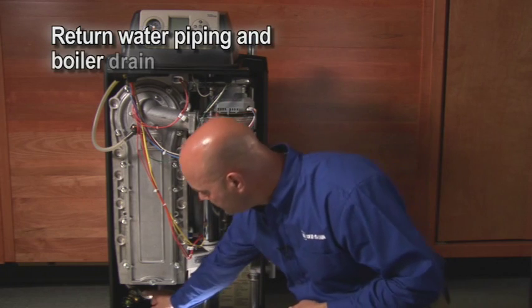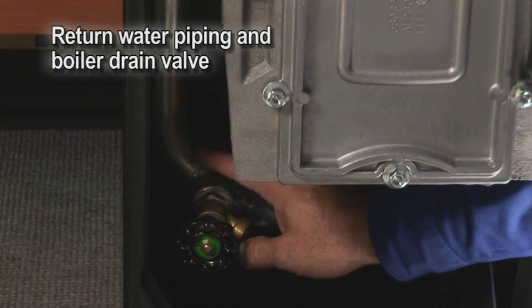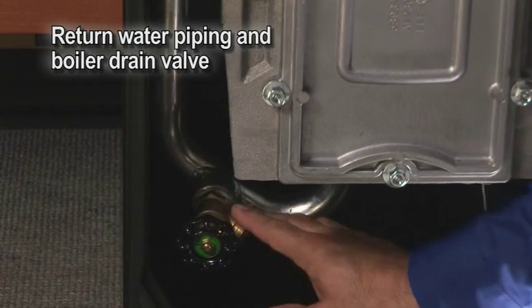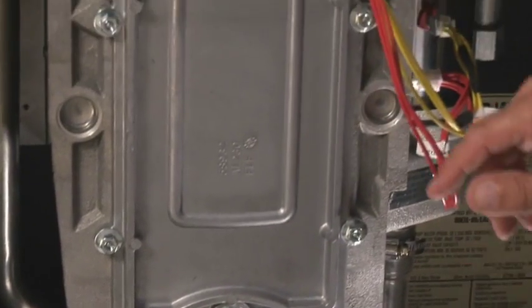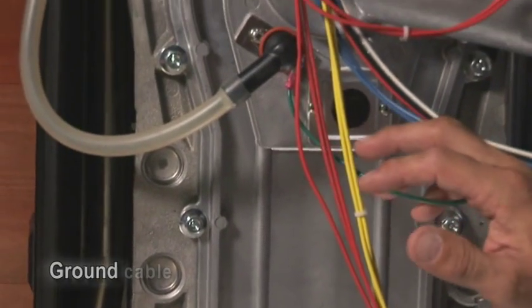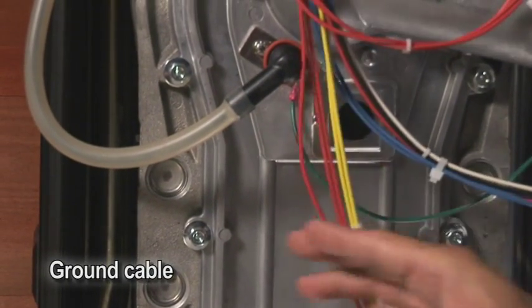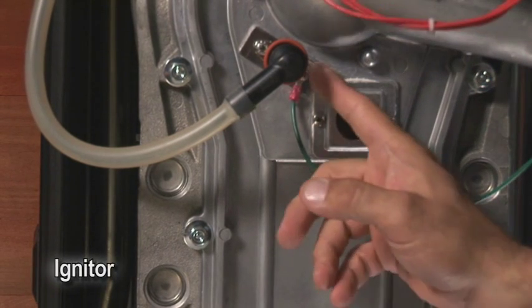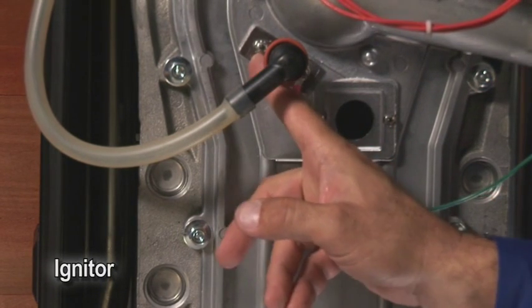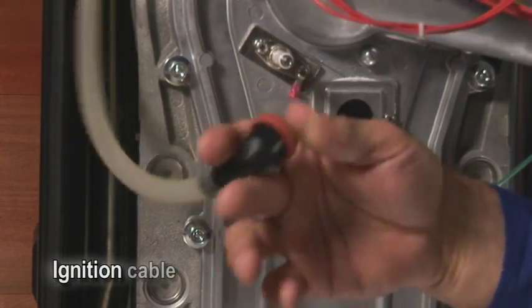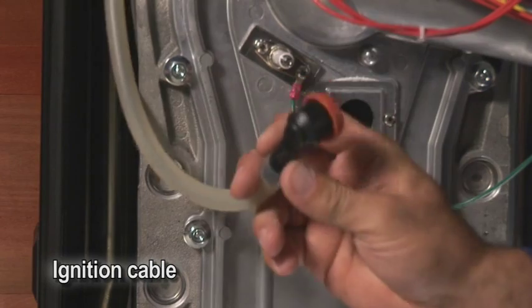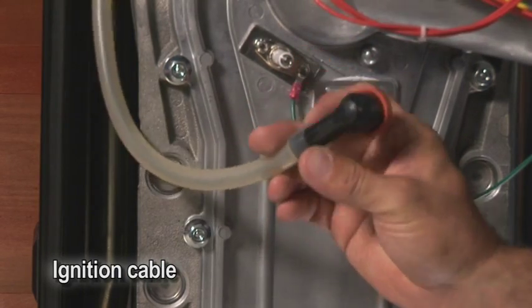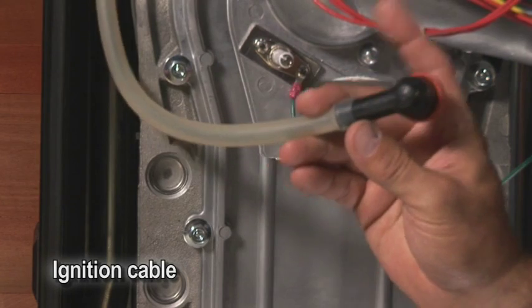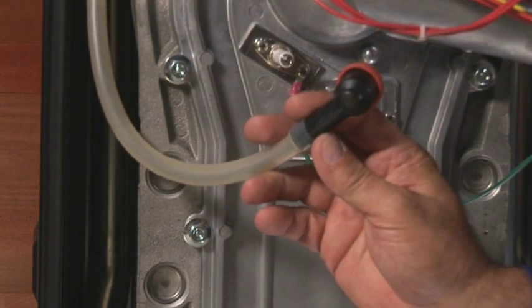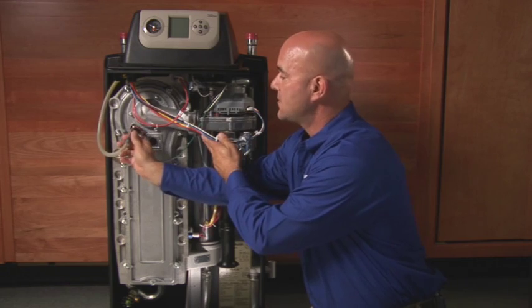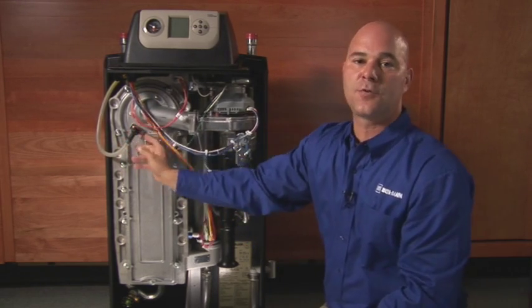The return piping is on the other side of the boiler right here. It comes standard with a boiler drain, already attached from the factory. Come up this side, there's a ground cable that's attached to the igniter. The igniter mounts directly into the front of the boiler with two Phillips head screws. The ignition cable plugs directly into the igniter. This cable goes up to the control, the spark comes down, and then we send a flame signal back up through this cable, which is displayed on the U-control screen. That's a tour of the heat exchanger compartment of an Ultra boiler.